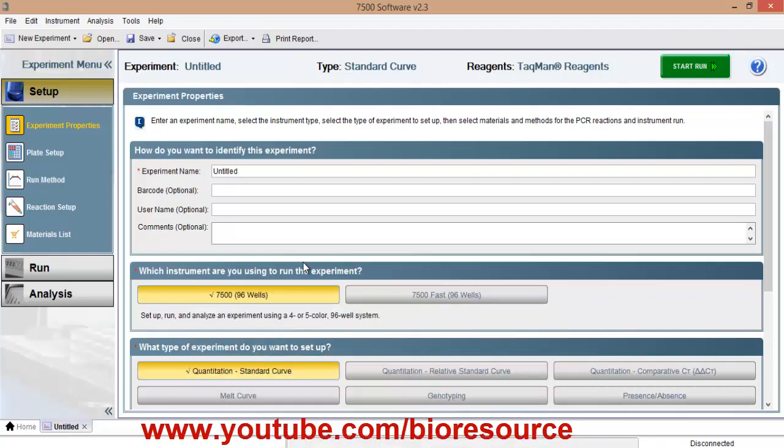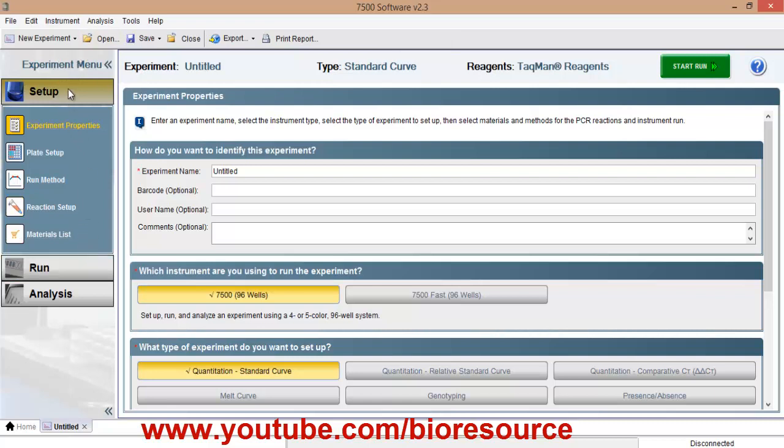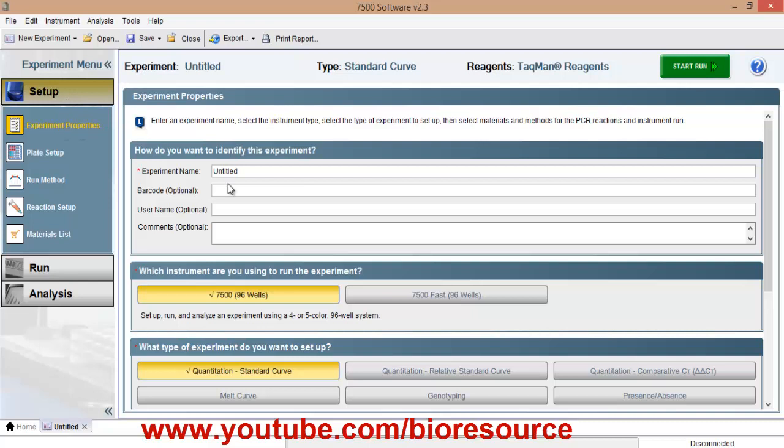Hello everyone, let's see how to set up reaction in ABI 7500 real time PCR instrument. So now we have opened the 7500 software. Here you can see multiple options, you have to go to setup and the experiment properties.